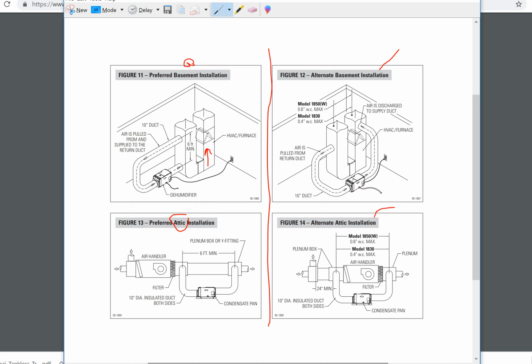The other thing is, when a dehumidifier discharges air, the air tends to be a little bit warmer than the air that entered the dehumidifier due to the process. And so by discharging the warmer air into the return, it's closer in temperature, so there's not as much variance on the actual temperature of the air entering the air handling unit. And by entering the warm air into the air handling unit, it can be cooled and further dehumidified before it's discharged into the space. So that's why that's preferred.